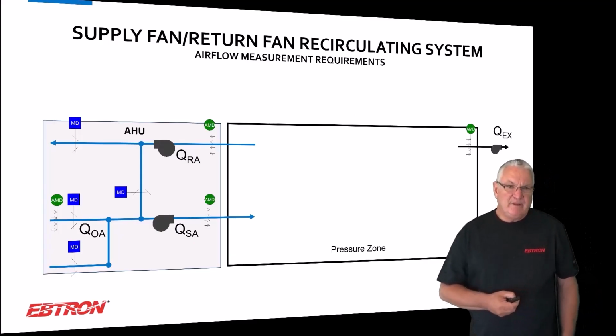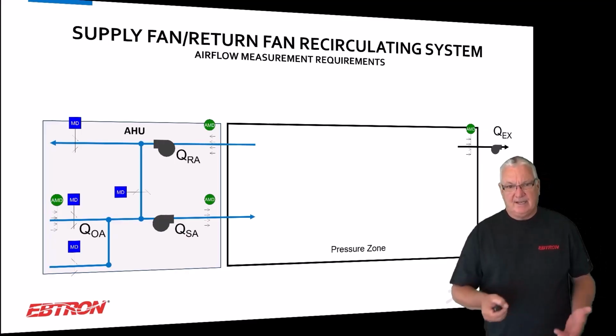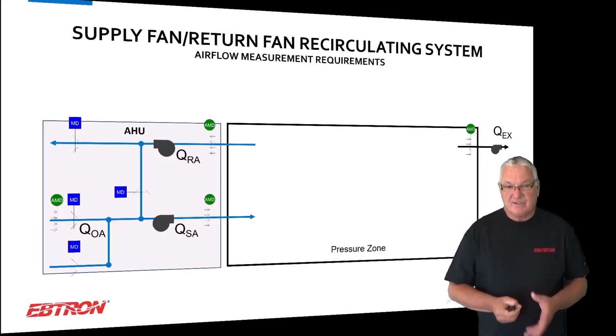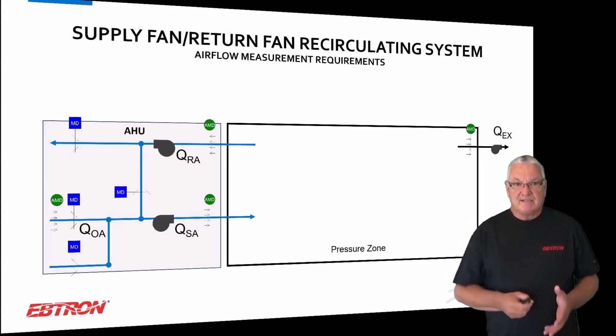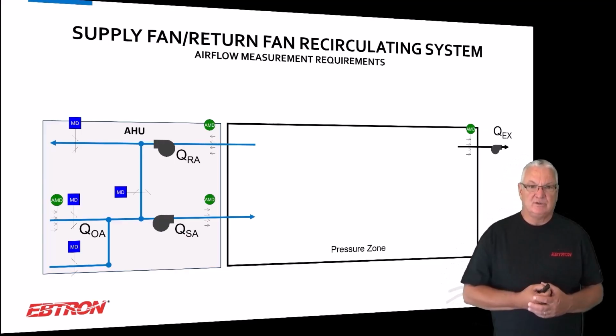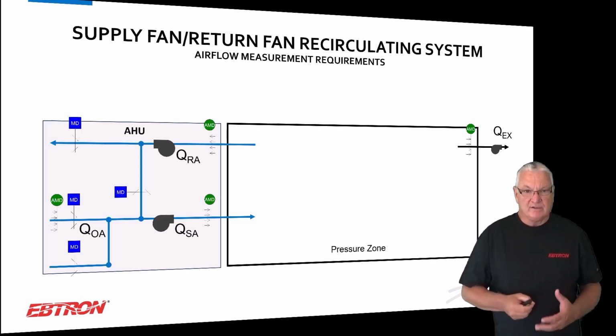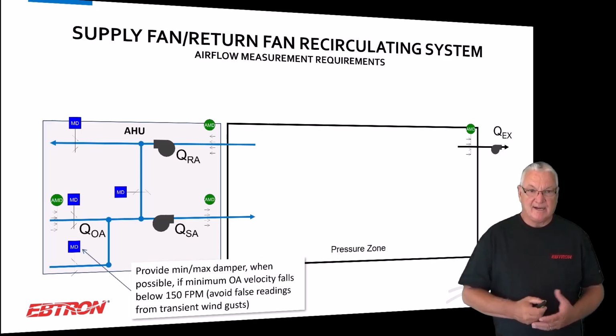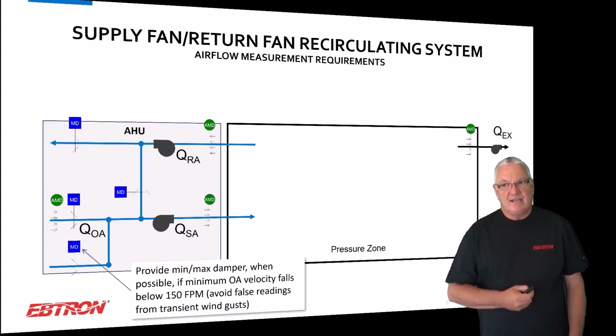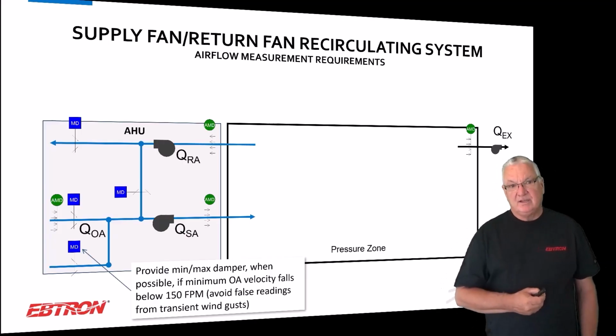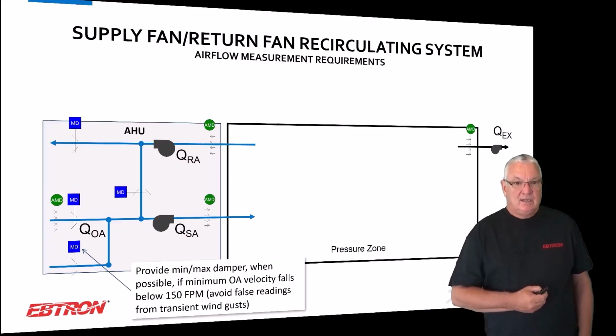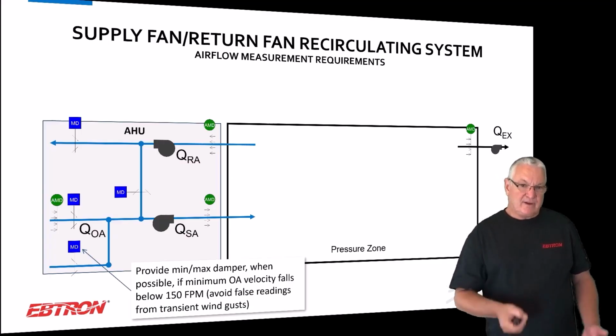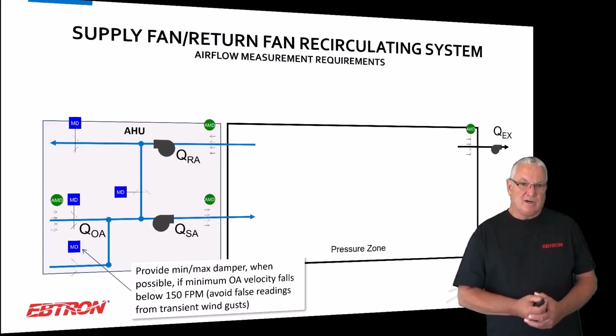Okay, so again, this could be anything. It could be any kind of a pressure zone, all right? We have a recirculating air handler. It's basically serving just one pressure zone. Okay, it's going to be different if we're serving more than one pressure zone. But if it's serving one pressure zone, we're going to basically locate the flow meters, supply, return, and at least minimum outside air. And if it's a rooftop unit and you really need good flow measurement accuracy, custom air handler, provide a min-max damper if the flow rates go below 150 feet per minute.